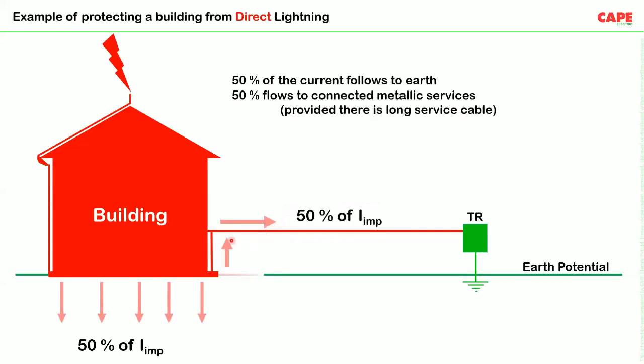So, SPD categorization. The SPDs connected at the mains incoming switchboard or mains incoming panel are called type 1 SPD. I have put a surname because in the old German standard, SPDs were called class B, class C, class D, a very old standard. Since we have the habit of still calling these devices by the old name, I just put it as a surname, but this is actually an invalid name. You should call them type 1, type 2, type 3 SPD.